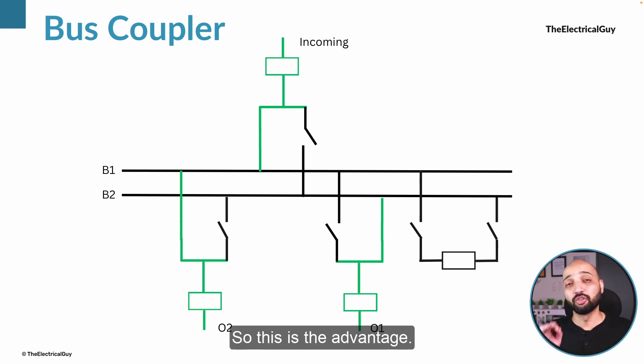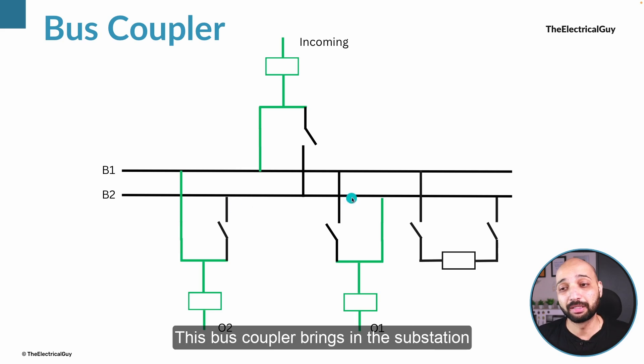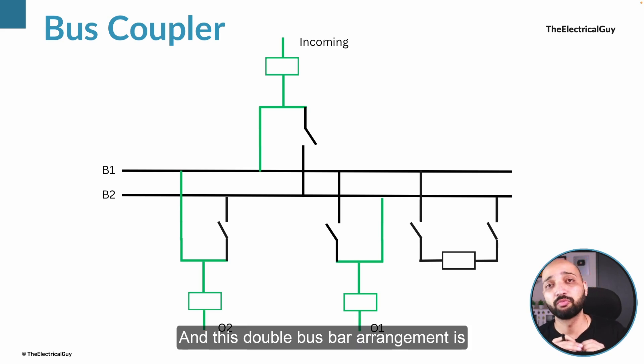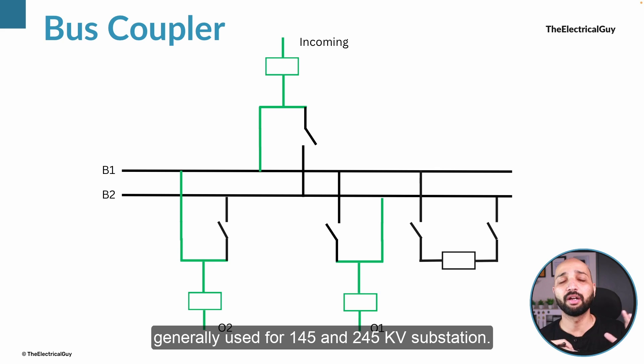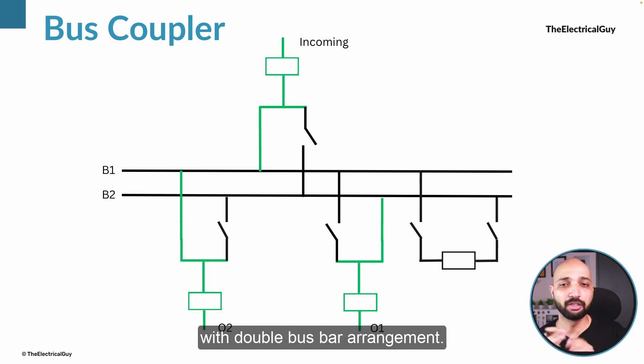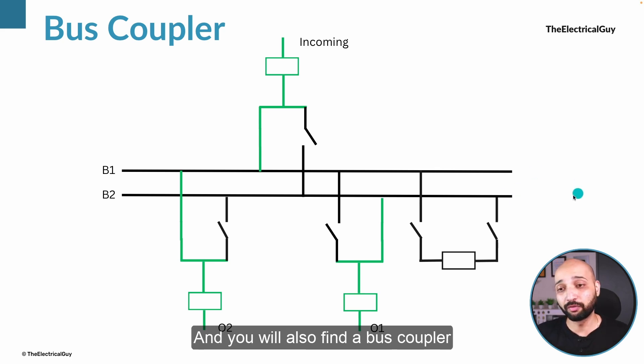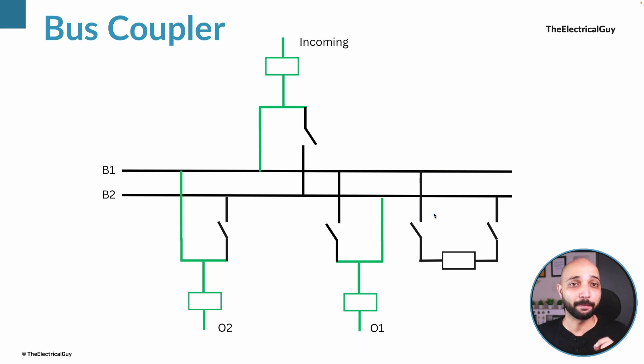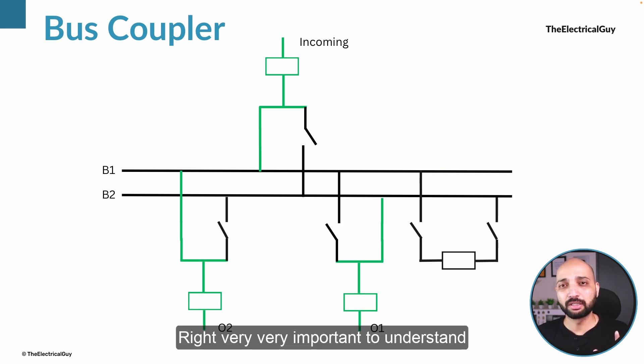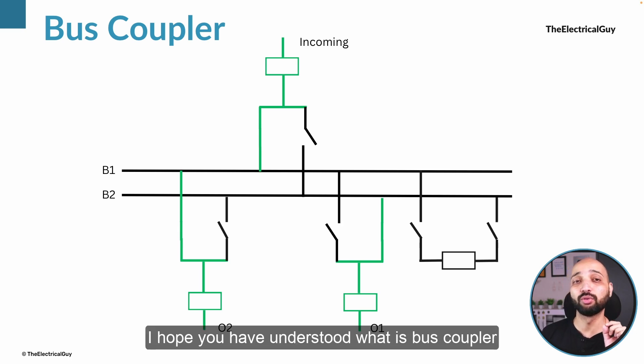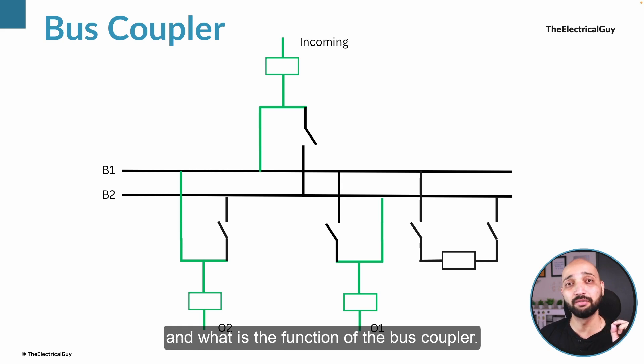This is the advantage the bus coupler brings to a substation — very important. This double bus bar arrangement is generally used for 145 kV and 245 kV substations. You will find the majority of substations at these voltage levels with a double bus bar arrangement, and you will also find a bus coupler bay installed in them. I hope you have understood what a bus coupler is and what its function is.